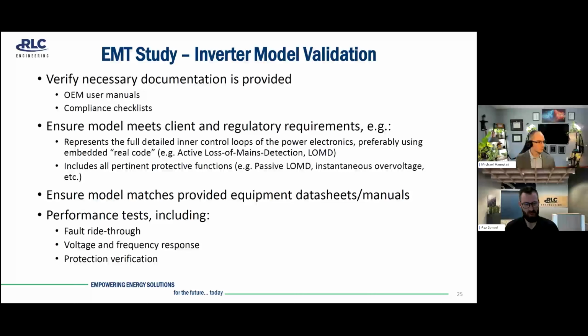Another requirement would be that it includes all pertinent protective functions such as passive loss of mains detection or LOMD, instantaneous overvoltage protection, etc. From here, we would ensure that the model parameters match what's in the provided user manuals or data sheets. So for example, do the real and reactive power output characteristics or PQ curve match the performance that's within the PSCAD model? And from here, we perform some standard performance validation tests, including fault ride through, voltage and frequency response, protection verification, and some others.